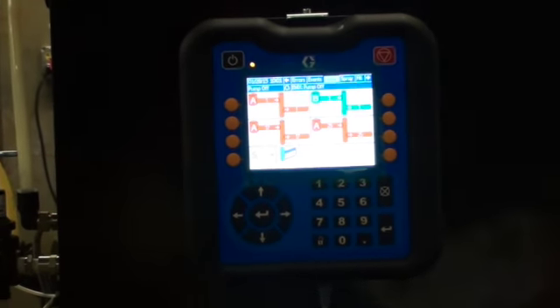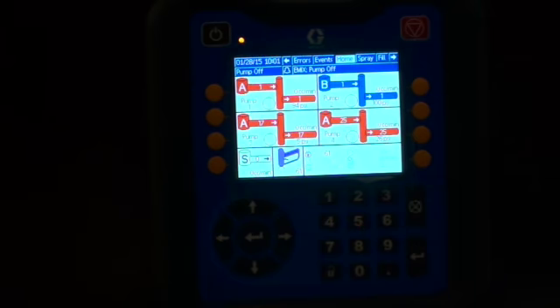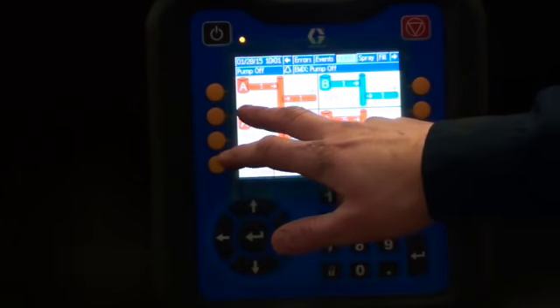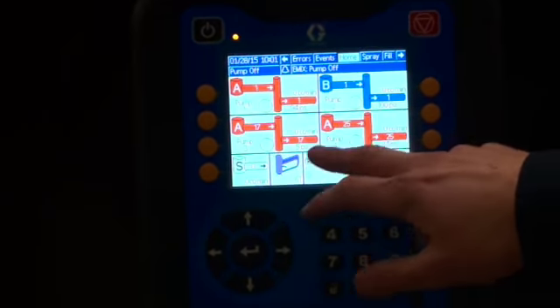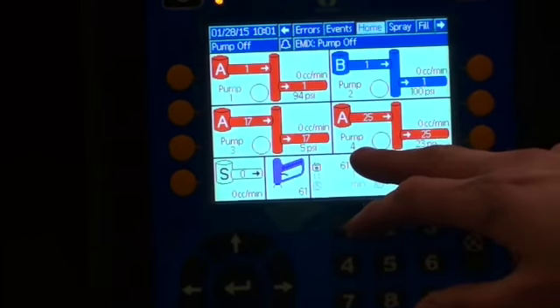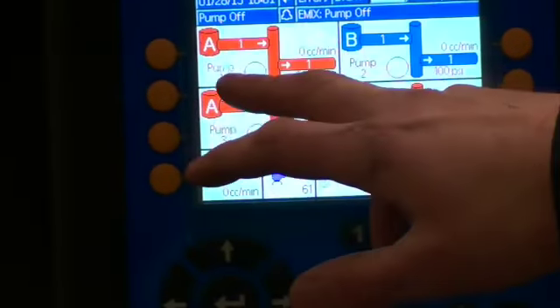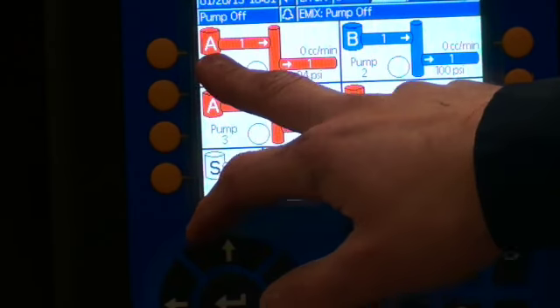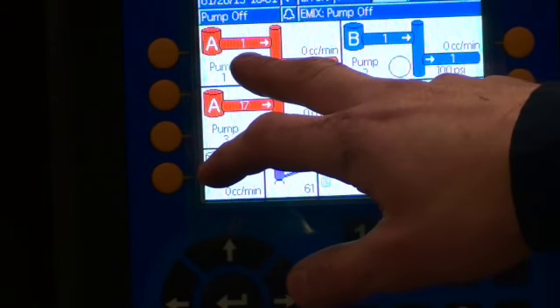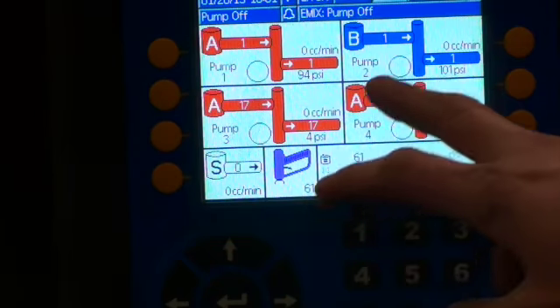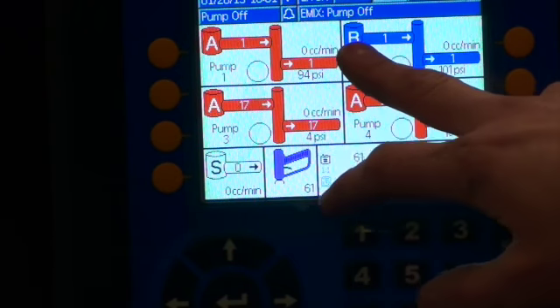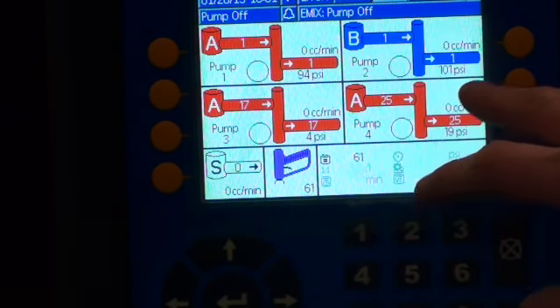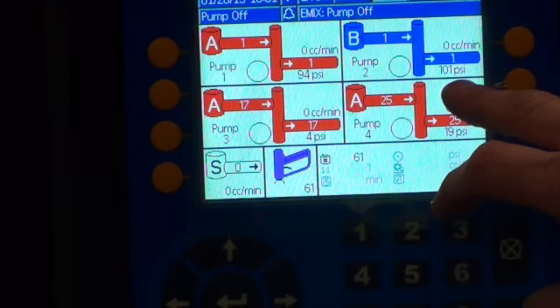Before we begin startup, we're going to go over the home screen here. On the home screen, you're going to see your pump 1 listed, pump 2 listed, pump 3, and pump 4. On that screen, you're going to see that pump 1 is loaded with A side, and that is color number 1. And then over here we have pump 2, which is always going to be your catalyst, and that's loaded as well. It has 101 psi inbound pressure.